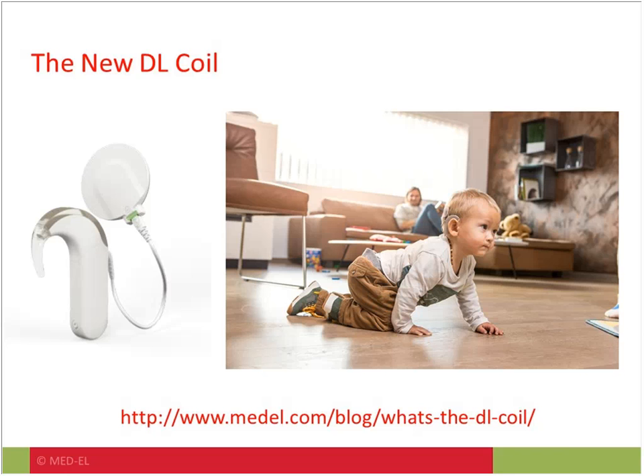The green light will flash 3 times when you turn the processor on, and it won't blink again if everything is working fine. Because it's easily visible on the coil, parents can quickly look and know with certainty that their child is hearing with their device. The red light, however, will flash once per second to indicate there's a problem.